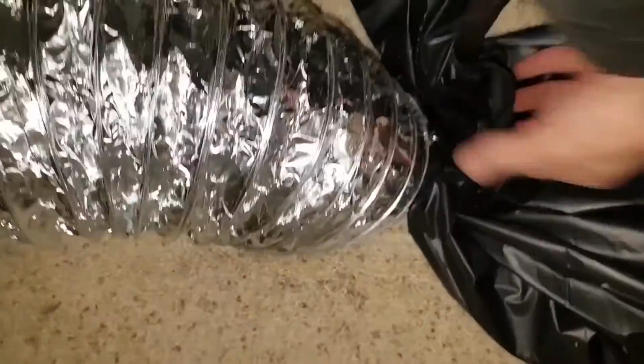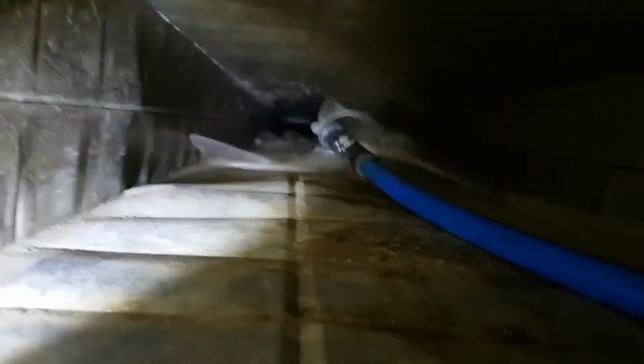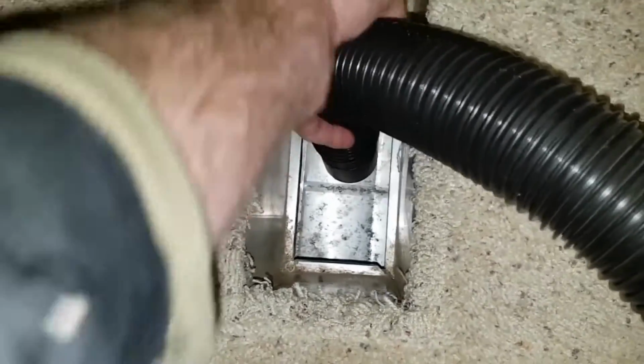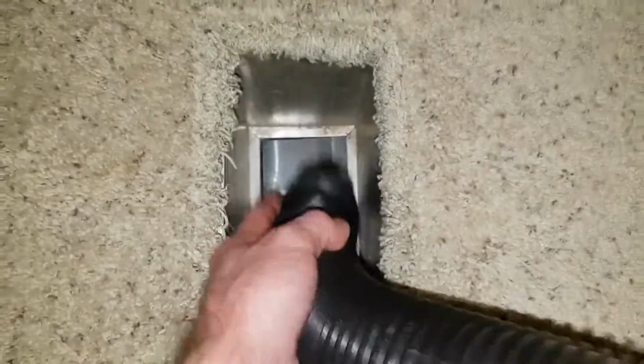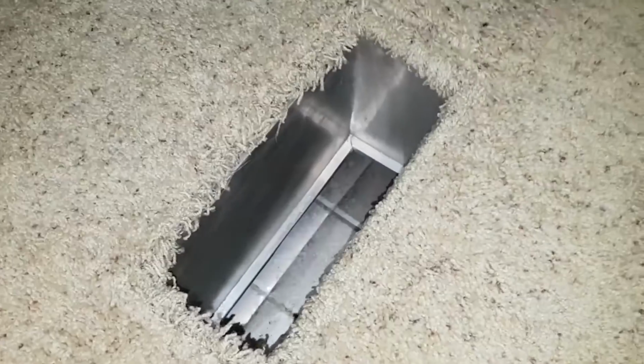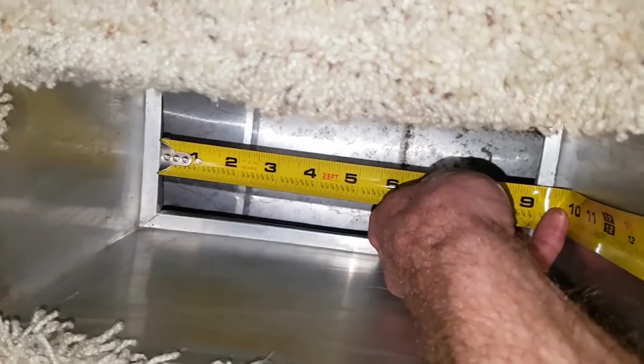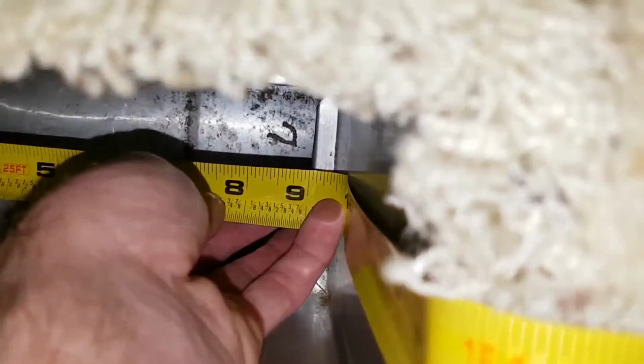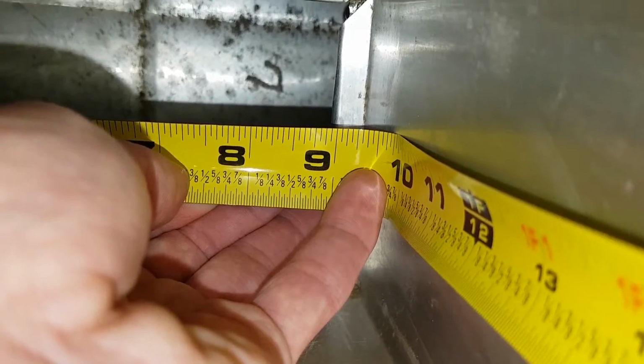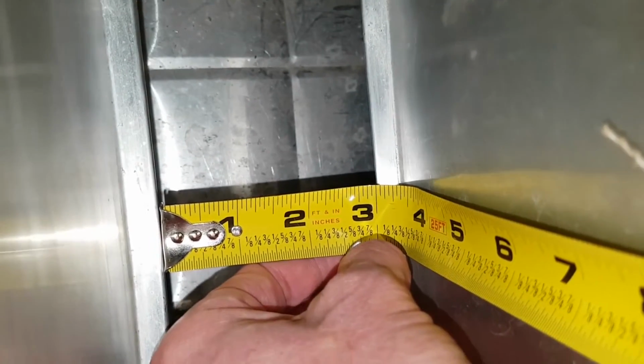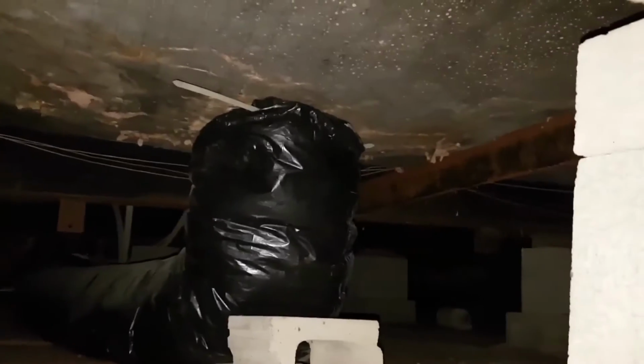After sweeping a segment was complete, the heavier debris needed to be removed from the duct opening using a shop vac. The leaf blower vac just wasn't strong enough to pull it upward through these vent openings. Another issue was this restriction. It's only about 9 inches by 3 inches. The ductwork I was cleaning was 14 inches by 4 inches, so that's quite a restriction.